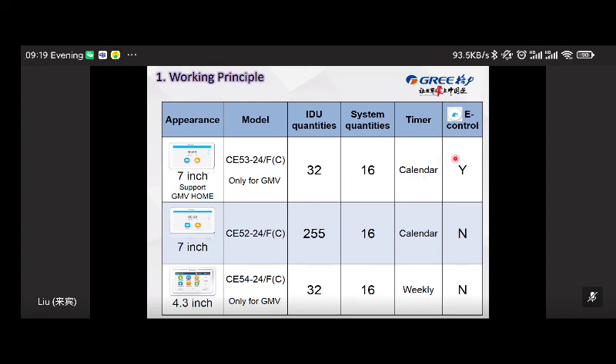For the e-control function, that's a special function only for CE53, only this central controller. It has the e-control function. E-control, you can consider it a preset. That means you can preset all of the settings, such as mode, temperature setting, and speed, and then you just press the e-control button and make the unit run as you preset. It's very convenient for the control.